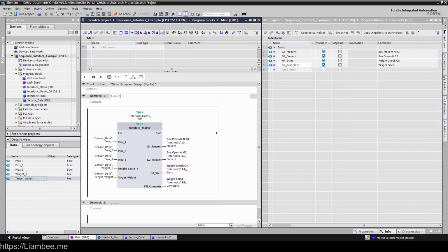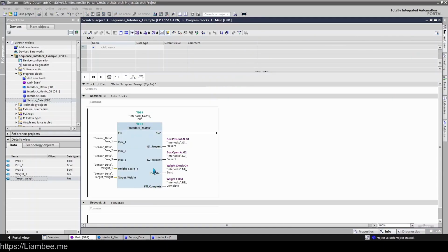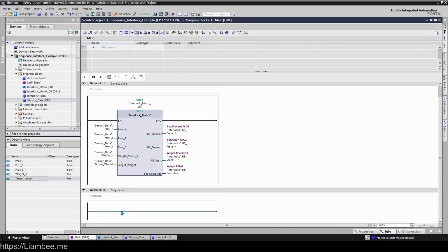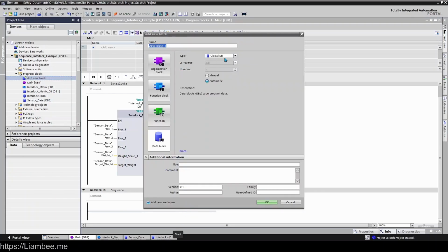So these interlocks give me everything that I need to tell my sequence to advance and for my sequence to actually do checks against, without having all the logic that's required to actually check, is the box at gate 1? Is the box open? I just need to have the supervisory sequence over the top now that actually manages the output, like taring the scale and releasing the box at the end. So it is a very, very basic example, but the principles around it are the same no matter the size of the sequence that you're doing.